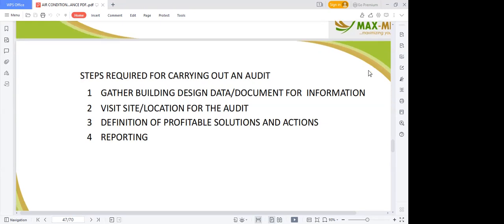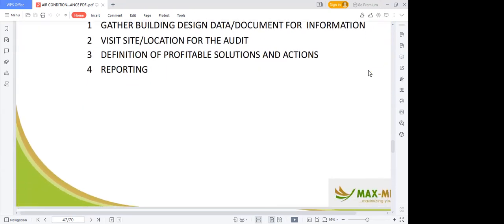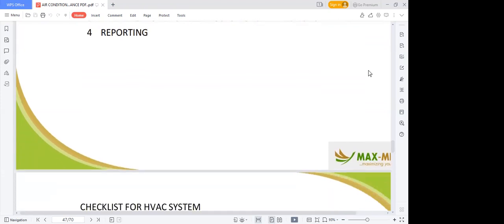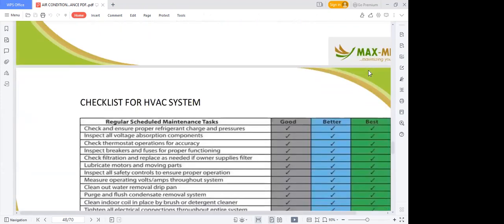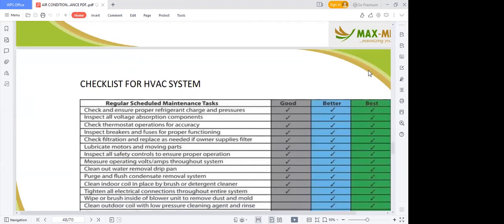After you've done your condition assessment, you must do what they call reporting. Then, checklist for HVAC equipment. When you have finally done this, in order, one of the solutions is for you to do what they call regular scheduled maintenance tasks. If your technician is going around, what are the things they must check to see that this unit is working well? They must check the condition and the cooling required for the unit. They must check if there's a drain issue.